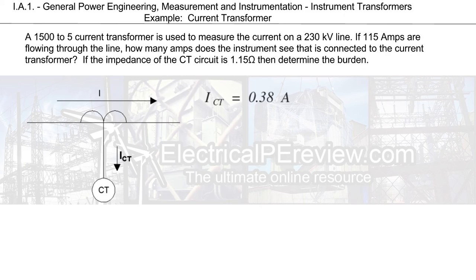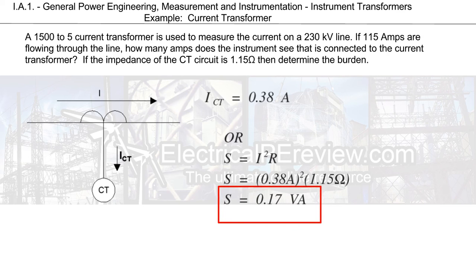Alternatively, another way to solve for the same thing, it's a little bit quicker. We can use our power formula of I squared R, plugging in our CT amps and solving for our burden. We arrive at the same answer of 0.17 volt amps.